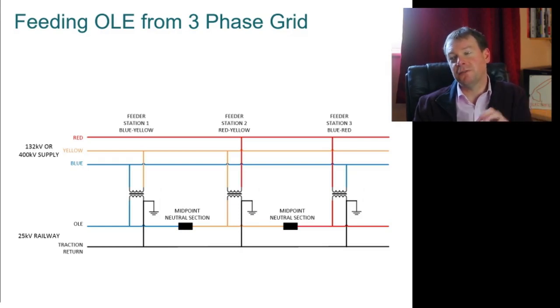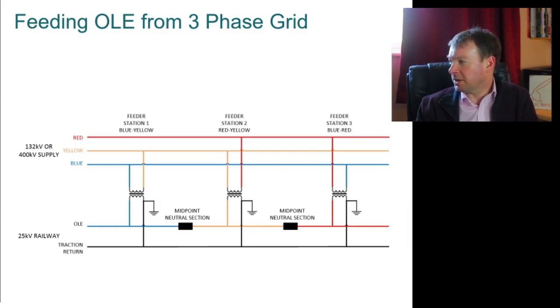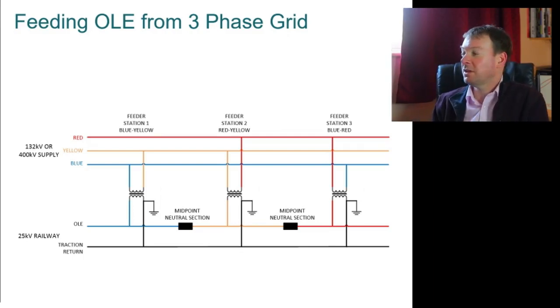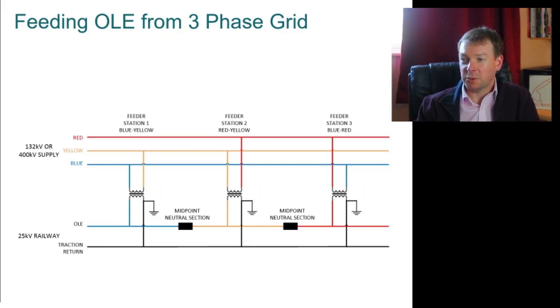This diagram shows the first feeder station taking from blue and yellow, the second from red and yellow, the third from red and blue, and we keep repeating that cycle. That helps limit the imbalance. The problem is you cannot connect those different circuits up, you must keep them segregated. So we have to have a neutral section midway between those feeder stations - a mechanical arrangement with insulators that we must have. It causes us some challenges: they can be difficult to maintain, and they can be a known failure point.